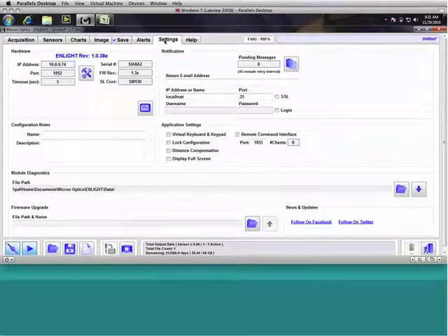In our application, it is important because we've placed two absolute temperature sensors at a very far distance. The relationship between wavelength and temperature is a complex third-order polynomial, which is very sensitive to shifts in the wavelength. And so it's going to be critical that we establish the correct distance to those sensors before we apply the calibration expressions to the FBG so that we get the correct temperature information out of those sensors.